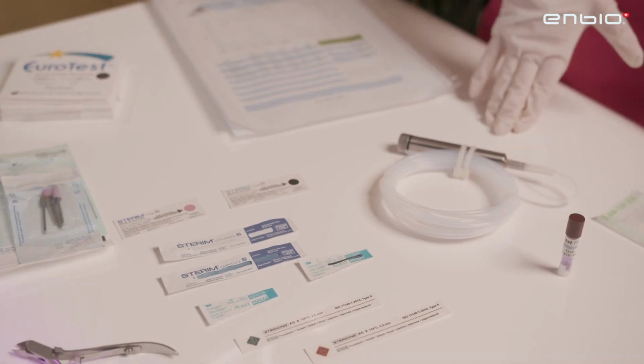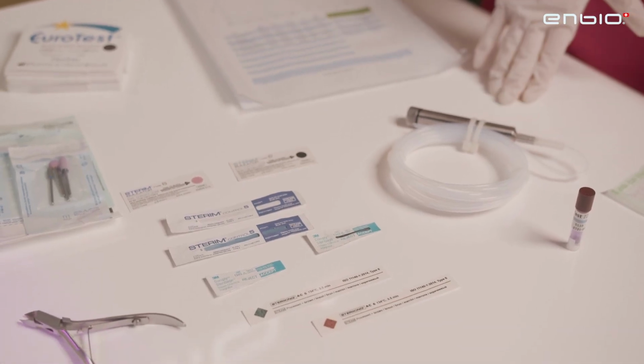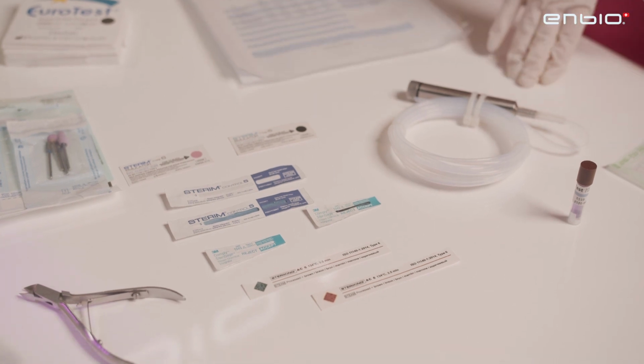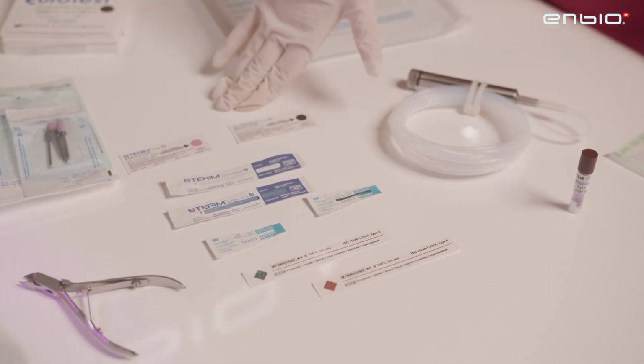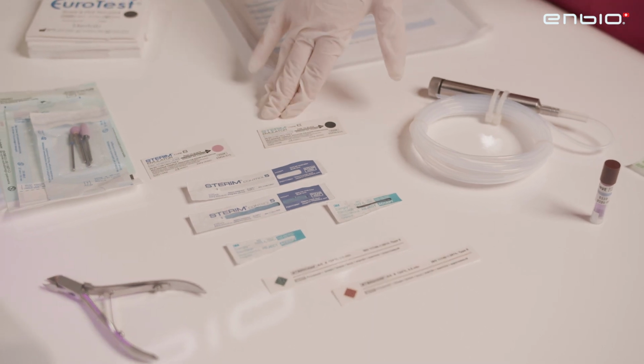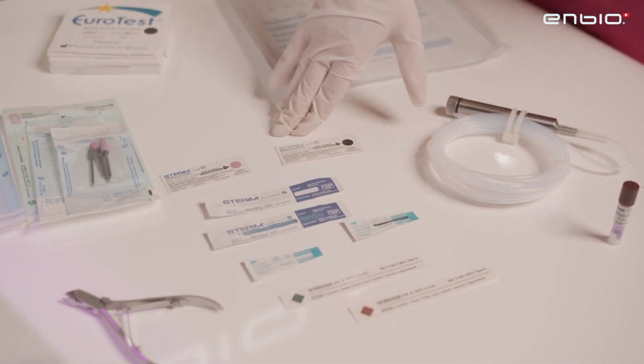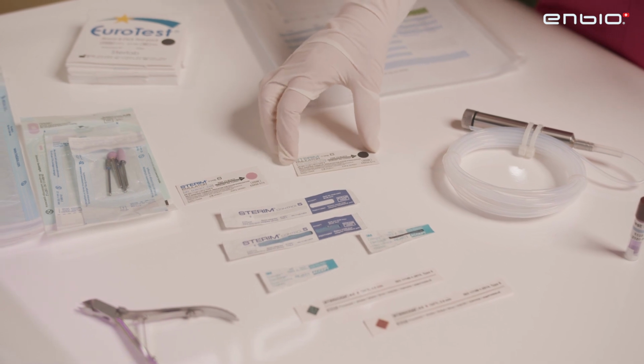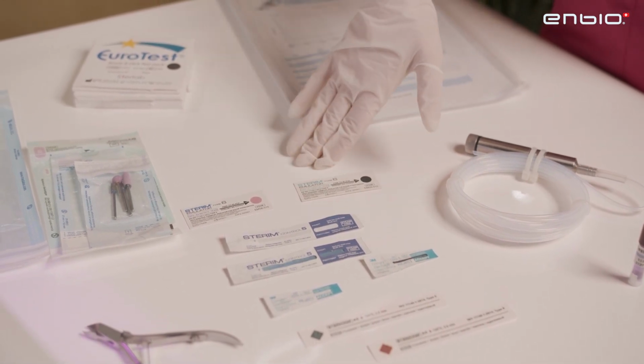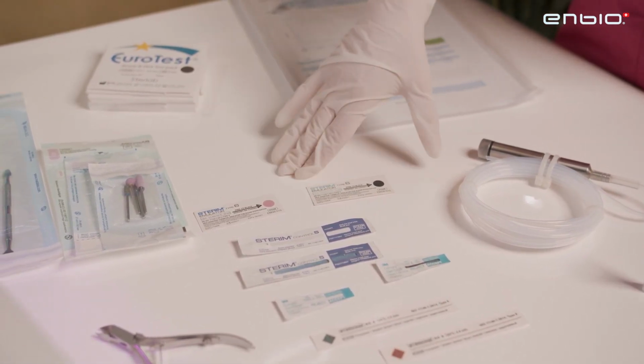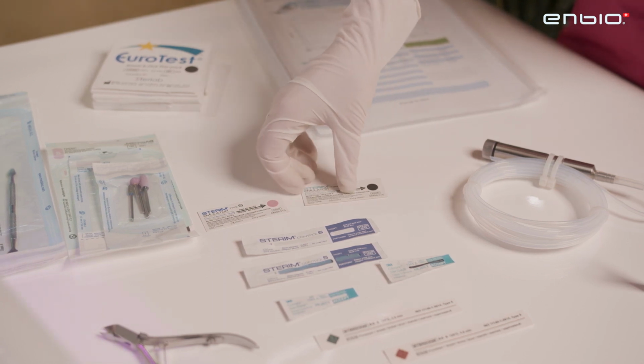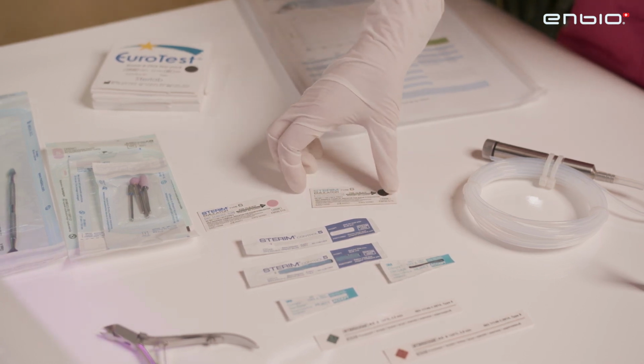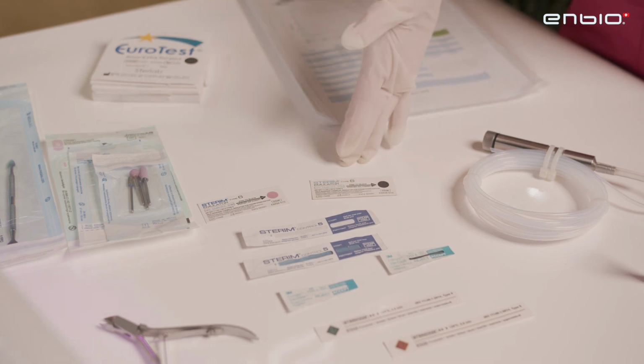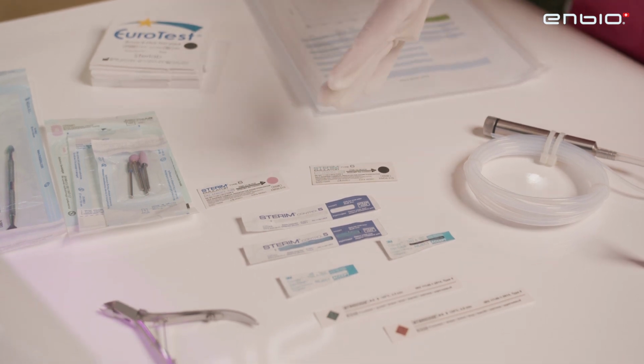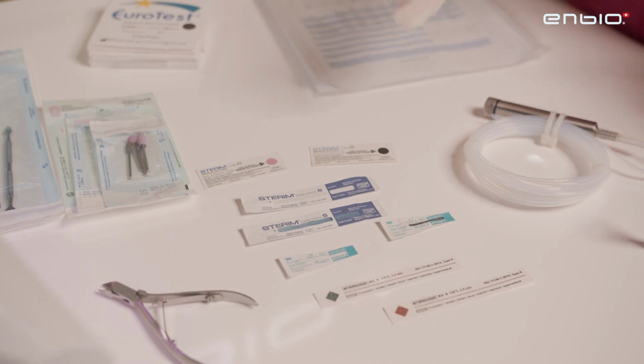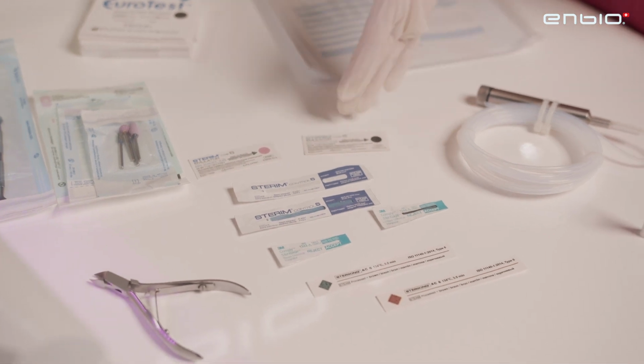Let's see how we can test the efficiency of the autoclave. There are different tests that we can use, for instance, chemical indicators. The chemical indicators are classified in 6 different classes, and we recommend the usage of classes 5 and 6 because these ones are the best. They practically take into consideration all the factors that are involved in the sterilization process, compared to the inferior classes, which take into consideration only a few of these factors.